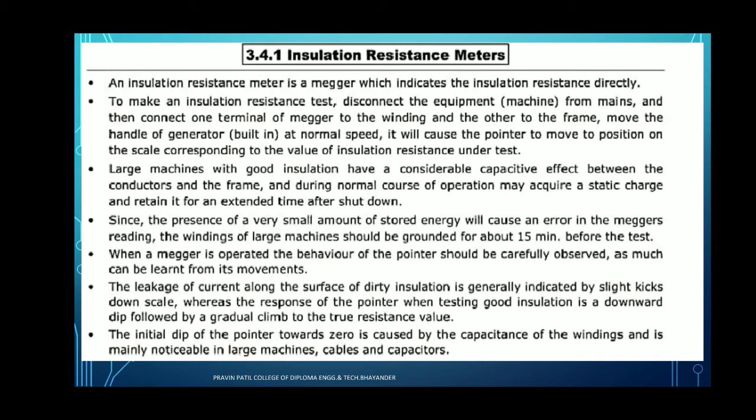The winding of the large machine should be grounded for 15 minutes before the test. That is essential. When the megger is operated, the behavior of the pointer should be carefully observed, as much as we have to see the points of the meter and the movement of the pointer.